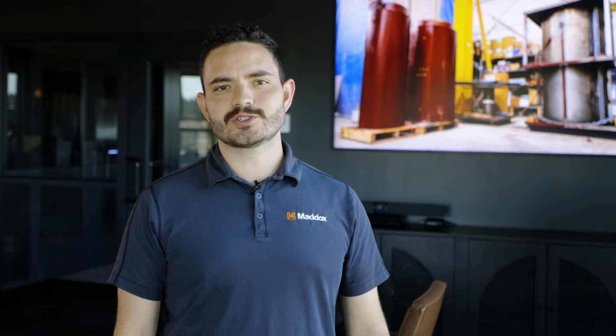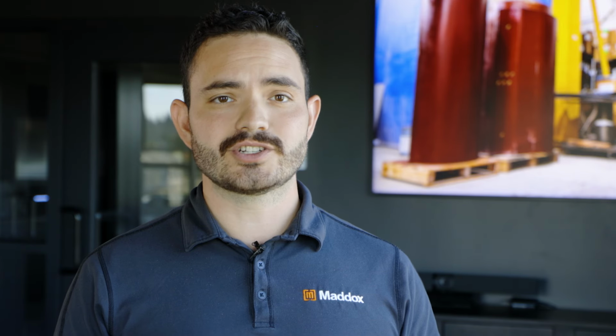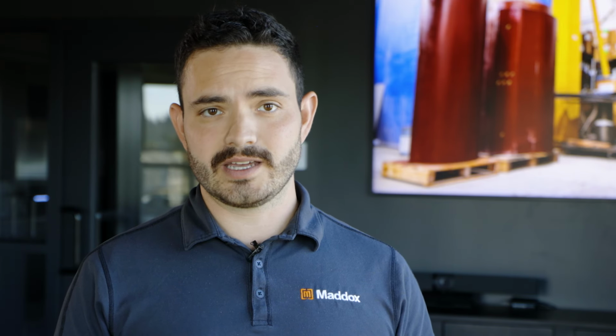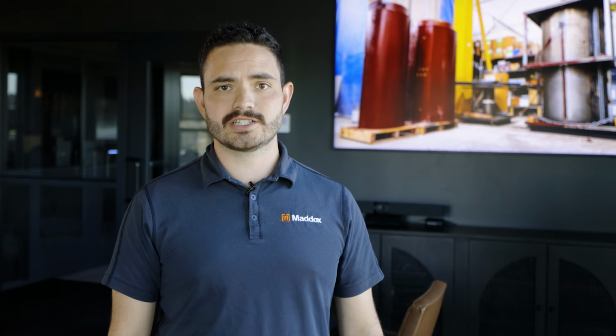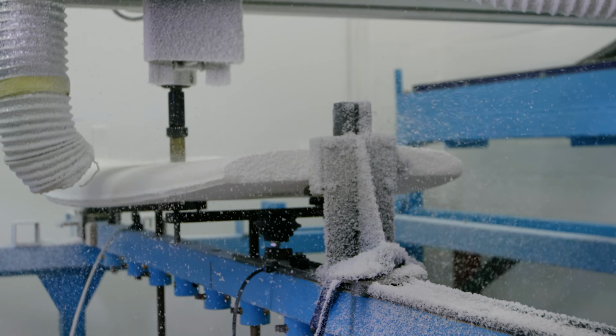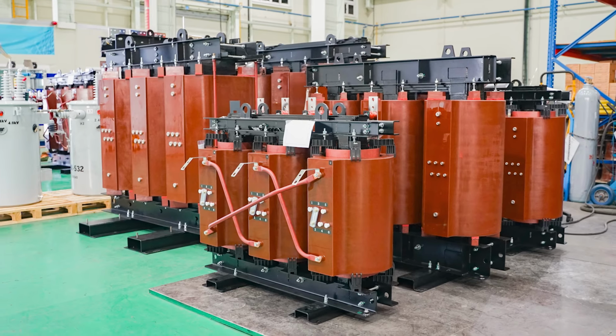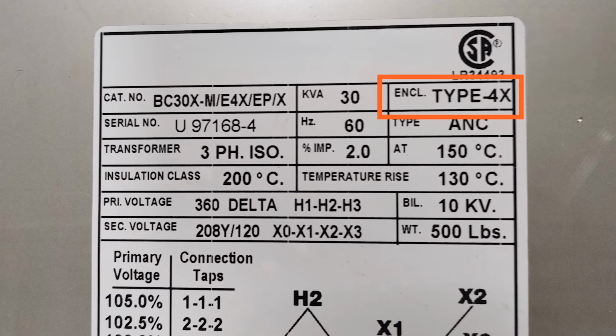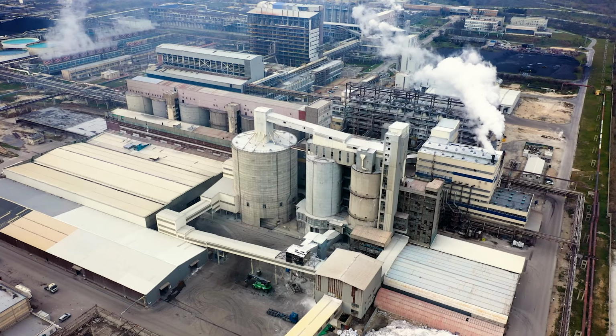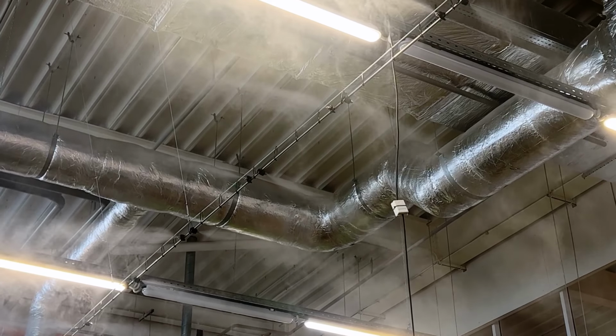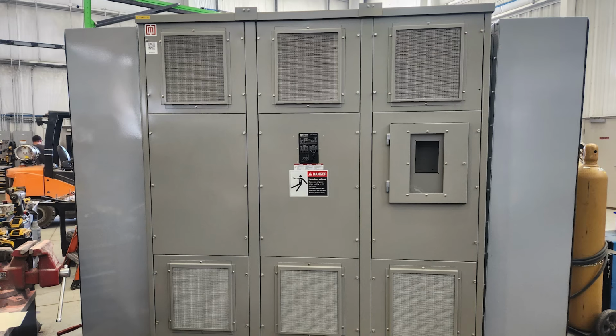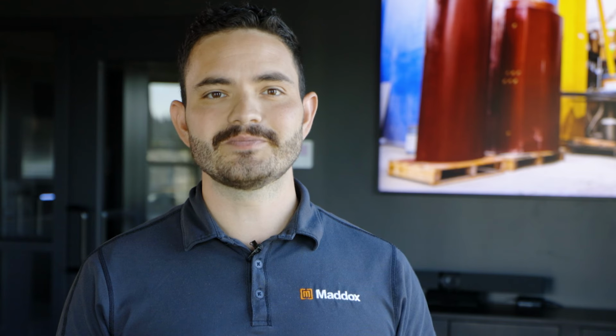If you're wondering whether you need winding protection, an enhanced enclosure, or both, you'll need to look at your specific application. Every transformer situation is different, but here are a few examples. If your transformer needs extra protection for both short circuits and excessive flying debris, a cast resin transformer with a NEMA 4X enclosure would work. However, if your environment is humid, but not overly corrosive, a cast coil transformer with a NEMA 3R enclosure would work.